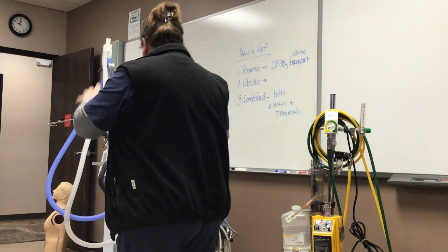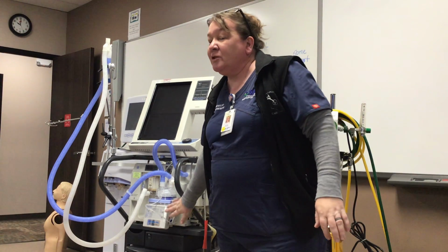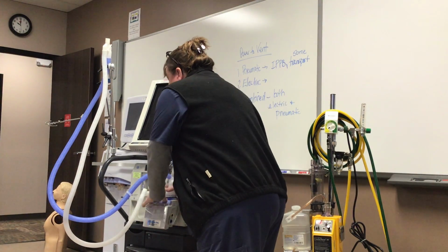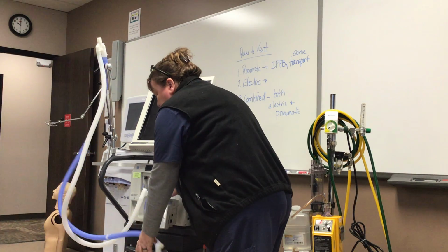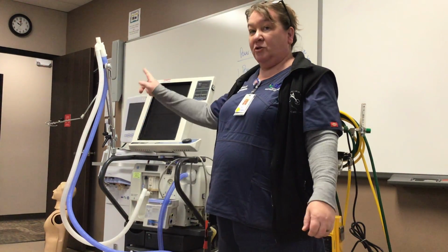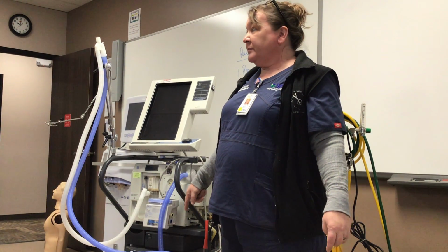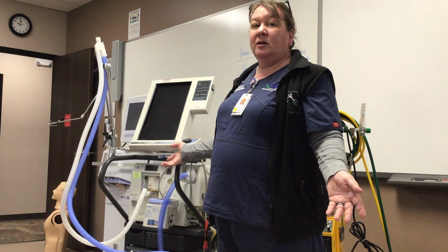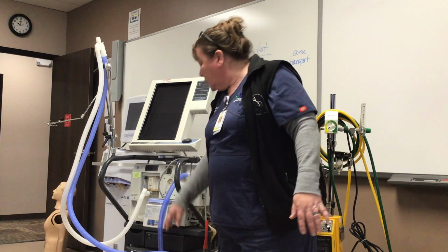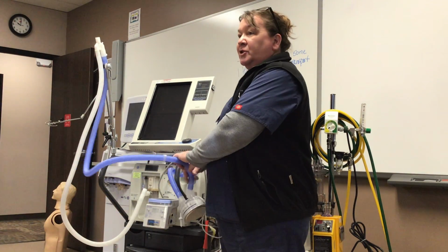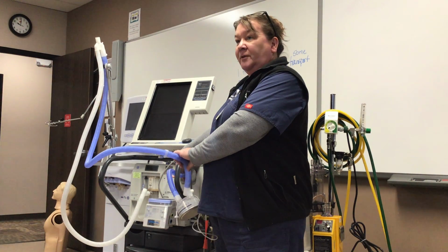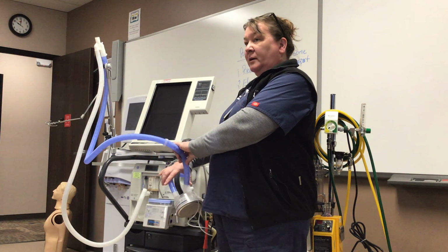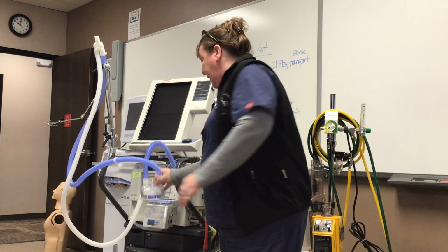You also need, well, let me time out for a second. So that's how that humidifier works. If you don't have this humidifier on here, the only difference is you're just going to let it hang like it was hooked up to the heater. That way you're practicing how to hook it up, because there's also wires that go in here as well. If you didn't have a heater and you were using an HME, you wouldn't use these extra parts in the water container. You would just take your circuit and hook it directly to the filter. And you would skip this part. Make sense? Okay.